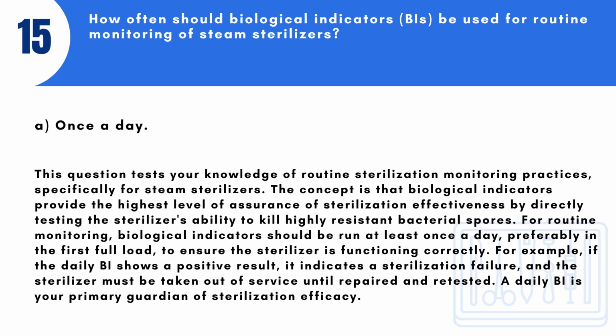For example, if the daily BI shows a positive result, it indicates a sterilization failure, and the sterilizer must be taken out of service until repaired and retested. A daily BI is your primary guardian of sterilization efficacy.